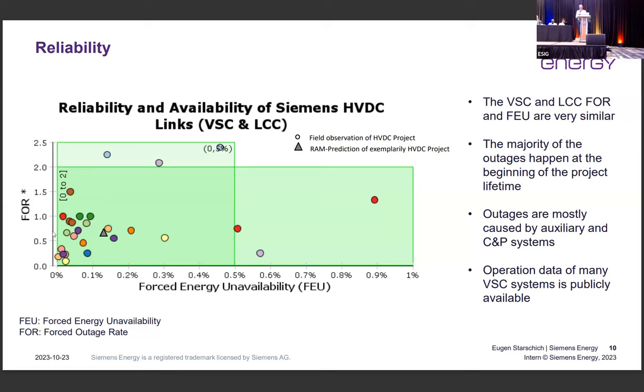And the good thing, which is also helping the industry, is that I can tell you our system is so reliable, but the majority of the VSC operational data is publicly available. For example, TenneT, the Dutch-German TSO, who operates the majority of the VSC systems, is required by law to publish the availability of their system, and also the availability of the HVDC system. Whenever there is a failure in the HVDC system, they publish it on the website.